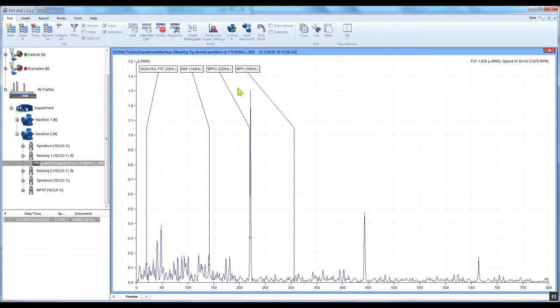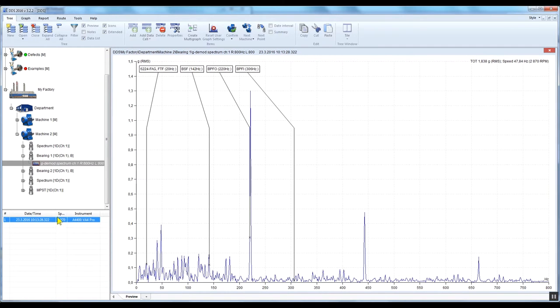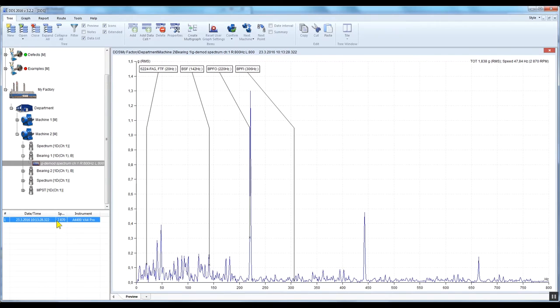In our example, we measured the speed using a speed probe, so this information was already included in the spectrum data cell. You can see the speed in the bottom left corner in the data list. If you did not measure the speed, you have to enter it manually into the measuring point or the tree item above. Speed measured by the speed probe always has priority over manually entered speed.